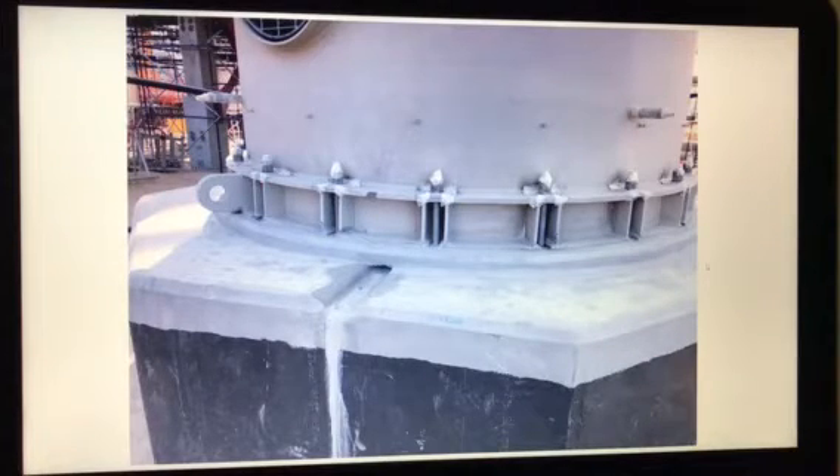When the vessel is erected, it looks like this. You can see the anchor bolt here, and some masking tape is put because those need to be welded later on. This is the foundation, this is the bitumen marking, and this extra layer here is called grouting. Grouting is done on the foundation — I will explain why grouting is done in my next step. This is how a vessel foundation is made, then the vessel is installed and grouting is done.